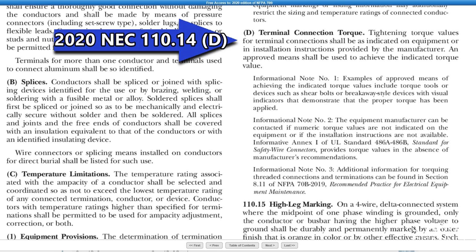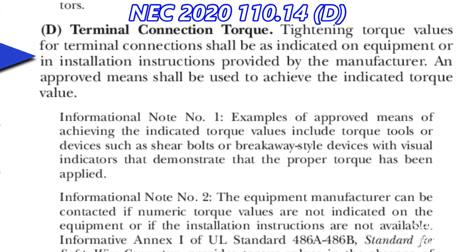First, let's see what the 2020 NEC has to say about terminal connection torque. Tightening torque values for terminal connections shall be as indicated on equipment or in installation instructions provided by the manufacturer. And an approved means shall be used to achieve the indicated torque value.